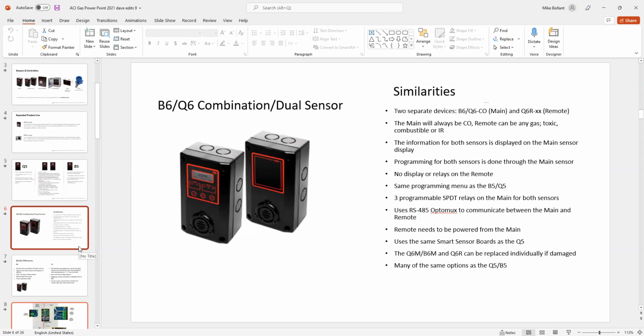The only difference is the secondary sensor. Let's say you're doing a parking garage and you've got CO and NO2, and you've got the CO at 5 to 6 feet off the floor, which is recommended, with the LCD on it, and the NO2, which is normally down around 12 to 18 inches off the floor in most instances. That won't have the LCD. Everything will read back to the CO sensor, so you don't have to get down on your knees and look to see if there's an LCD. Everything will read and be controlled by the CO sensor on the Q6 version. The reason we took the LCD off was so we could be more competitive as far as combo sensors go.